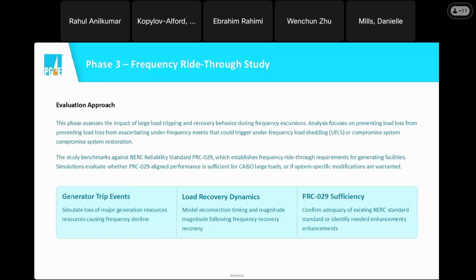You can think of that as something similar to what we'll be looking at on the voltage side as well. But for this, we're seeing a common theme of starting with the PRC-029 standards and then seeing how those need to be tweaked for large loads, and soliciting feedback on whether some of the requirements from the PRC standard, even though designed for more inverter-type generation resources, can also be met by data centers. Those are things we're going to be exploring as part of this effort. If we can move to the next slide, please.